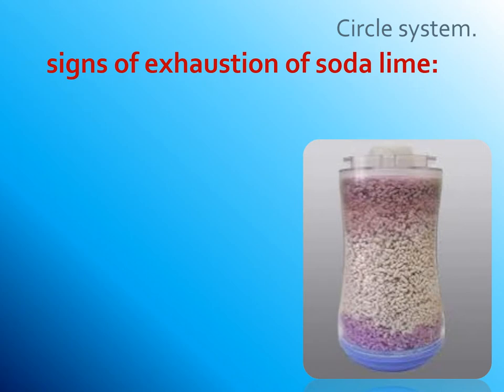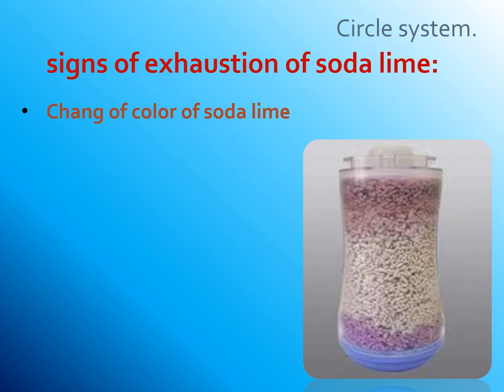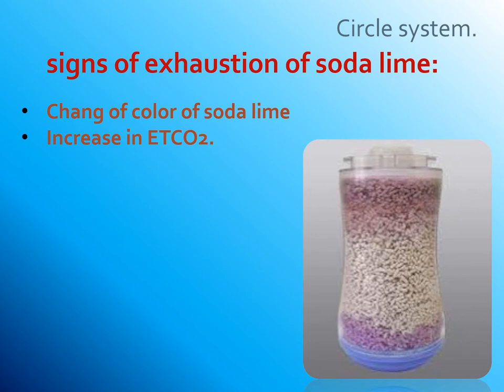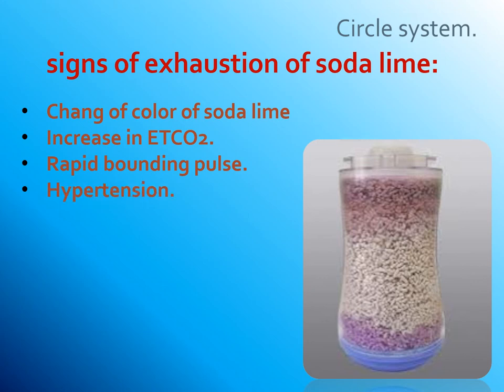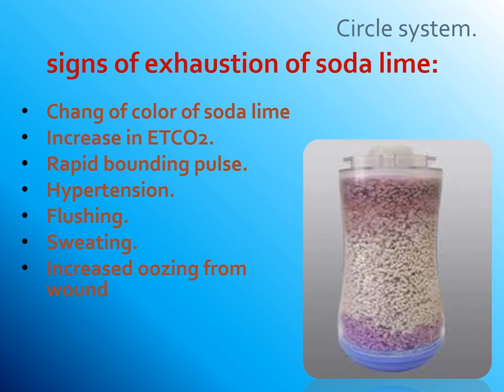Signs of exhaustion of soda lime — meaning it can no longer perform its function. First, the color of the soda lime: it is equipped with a color indicator that changes color when exhausted. Note the difference in color between active and exhausted soda lime in the canister. Other signs include: increase in end-tidal carbon dioxide, rapid bounding pulse and hypertension, flushing, sweating, increased oozing from the wound, respiratory acidosis, and arrhythmias due to rising carbon dioxide levels.